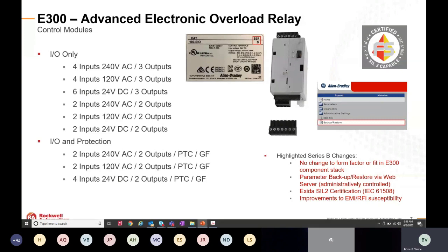One of the things we mentioned was the CCW interface for the E200. One of the really nice things about the E300 is that it also does not require any software. So once you configure the device, if you're using the Ethernet IP module, once you configure your IP address, you can simply open up a web browser, so Internet Explorer, Google Chrome, Firefox, and type in that IP address, and then that brings up an embedded web browser. So all you need then is that web browser, and you can configure the device, monitor the device, and look at all the different trip histories and things of that nature. So again, you can do everything you need to with the E300 without software. However, as I'll talk about coming up, you can use Rockwell software to integrate with this device as well if you're using that type of control system.